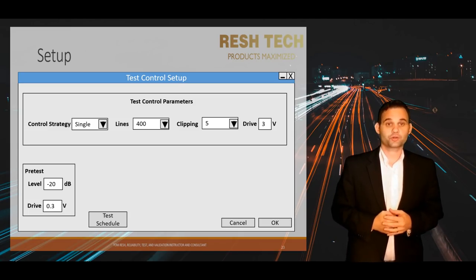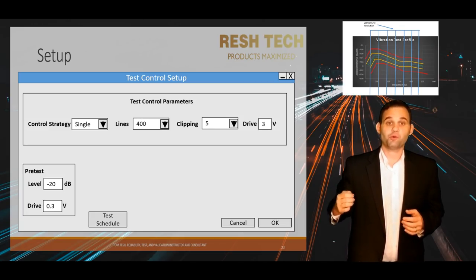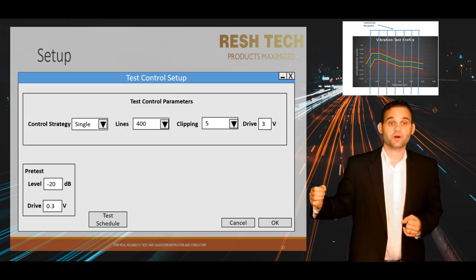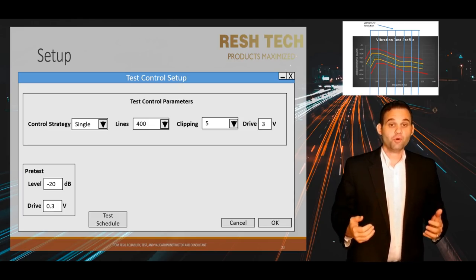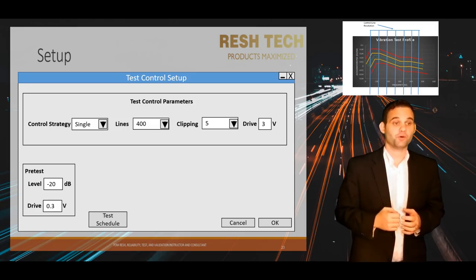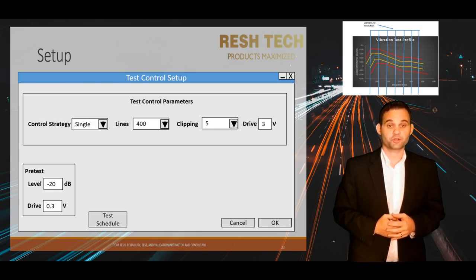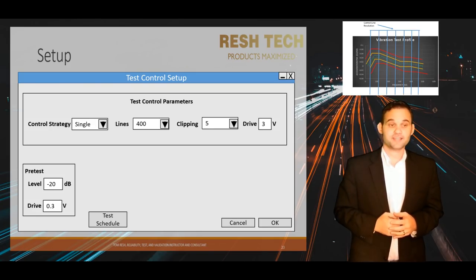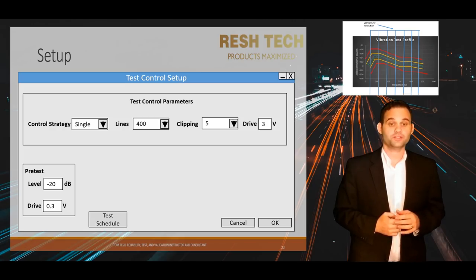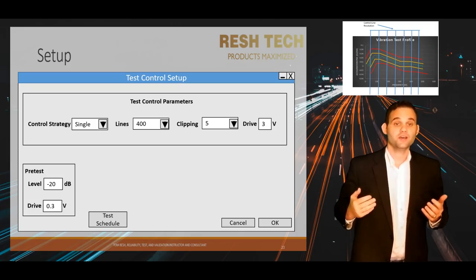Next up is lines or control lines, also called lines of resolution. This determines the number of points or frequency bands your controller will use to compute the next drive signal output. The higher the number, the more control you will have following your test profile values, as more points are factored in. However, this also slows down the response time of your controller, and you may not see a test issue in your control line until it is too late.